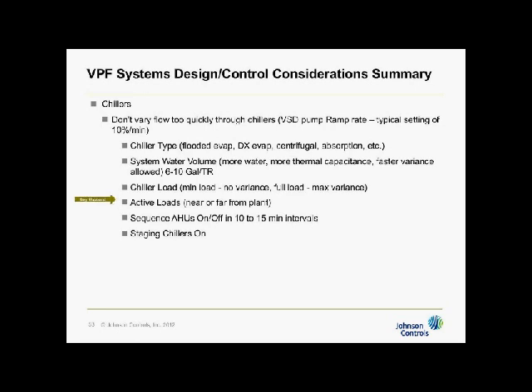Right? Active loads, where the loads are active in the system. If you remember that from the speed chart we were looking at in the head, where you got the head area, when the loads are active far away from the pumps, then you're going to higher heads and higher speeds. Well, the same thing kind of happens here. The loads that are active far away from the plant means that gallon of water leaving takes longer to return. So even though on average it might be 20%, when all the loads are active far away, you can actually go to 30. On the other hand, if the loads were active close to the plant, then it might drop to 10. So you see, the important thing to gather from this is that there is no one number for all conditions, and it varies all the way from 5 to 30%.